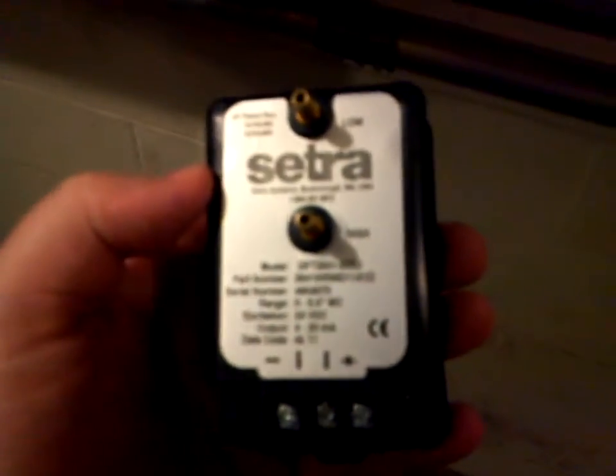Hey guys, in this video we're going to be talking about the Setra pressure sensors. We use these to sense the discharge pressure within an air handler system. They can also be used to sense a vacuum pressure as well. It depends on whether we use the high side or the low side. This particular unit features a high side and a low side. The difference between those two points is the high side is set up for sensing pressure, and the low side is to be used when sensing vacuum.